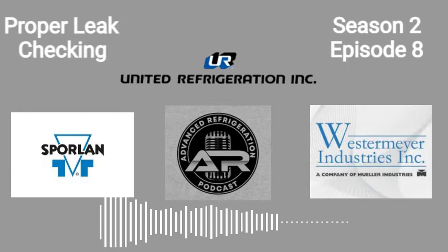If I don't find anything in the rack room and don't see any oil anywhere, I'll move on and check the condenser. Wait, I've got to stop you here, you don't shut anything down? Not in the first initial sweep, no. This is how I do it. I sweep the rack room. If I don't find anything, I move on to the condenser. I pop my head up there, make sure there are no fans through it, nothing leaking, check the PRV vent upstairs by putting the leak detector in there, and make sure nothing has come through the PRVs. Then I'll go down to the cases and walk-ins.